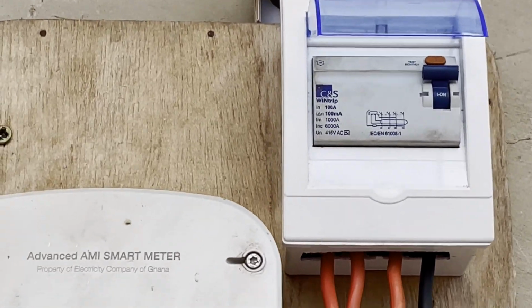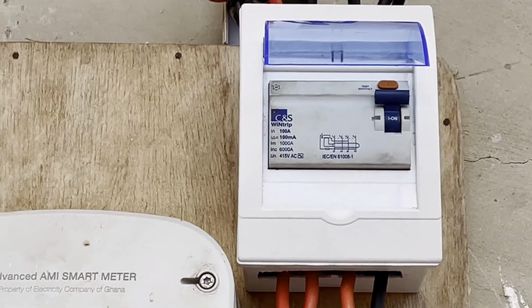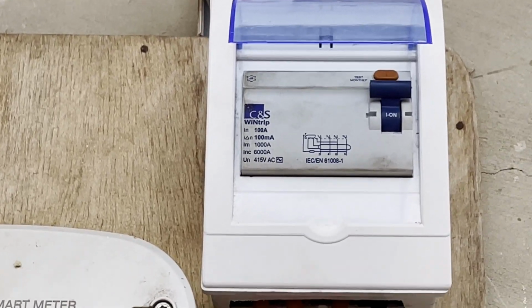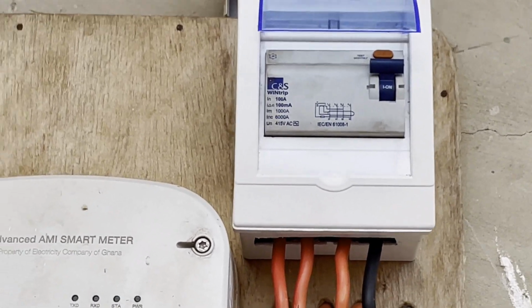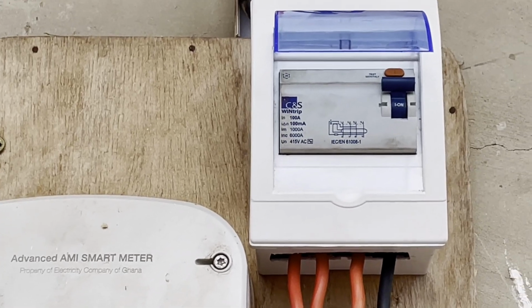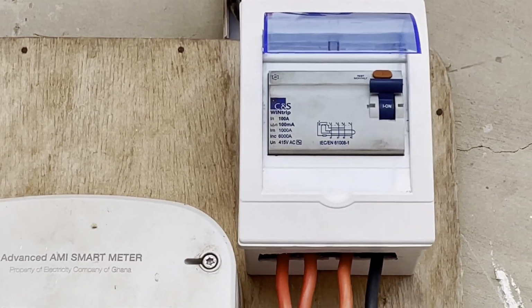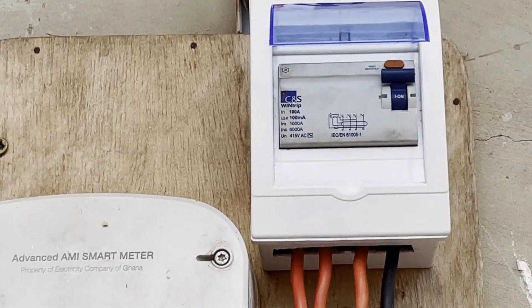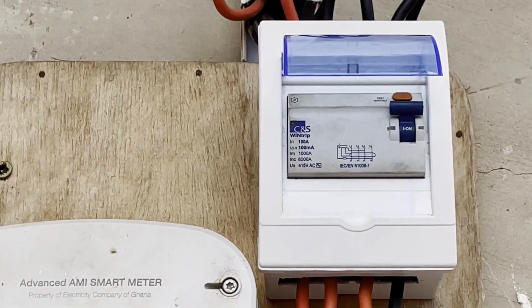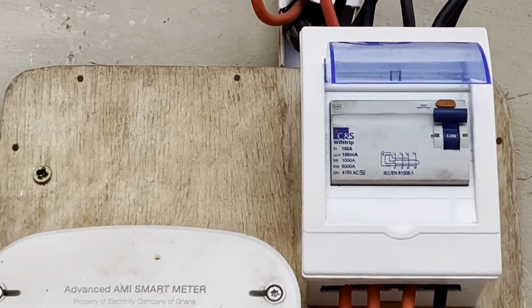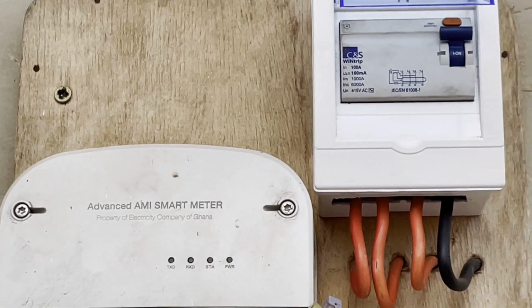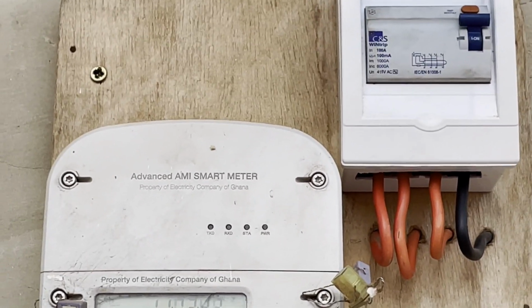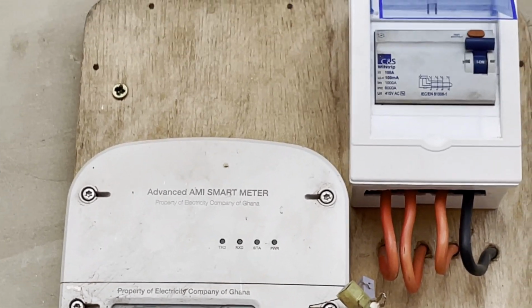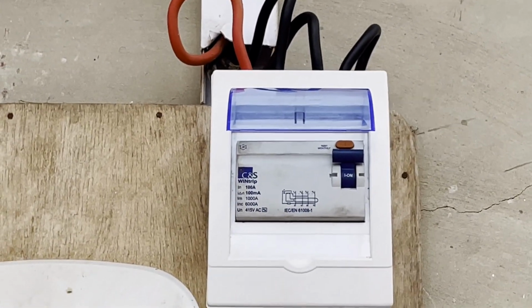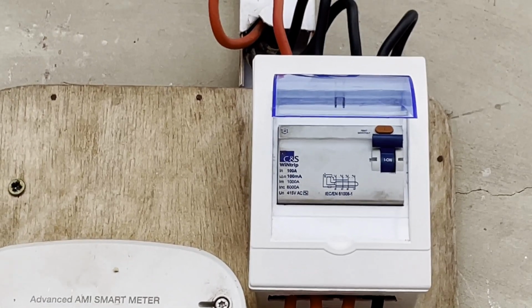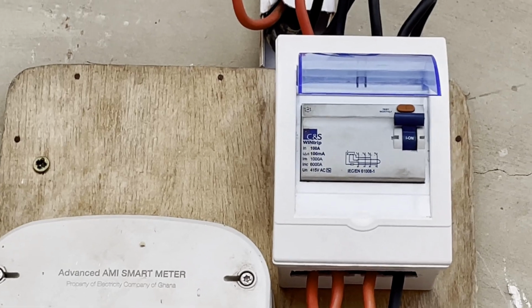Now, obviously, we go around a number of clients' homes. There are some clients' homes where the 100 milliamp sensitivity does not work - it trips so much, as soon as you install it, it just trips. So in some homes we install a 300 milliamp RCCB. The ideal number is 100 milliamp sensitivity, but this largely depends on the types of electrical equipment you have in your home. Different types of equipment, different manufacturers, they leak current to the earth. And the more current is leaked to the earth, the more nuisance tripping you can get with this incoming device. And what you don't want is you're ironing and then all of a sudden the whole power goes off in your house.